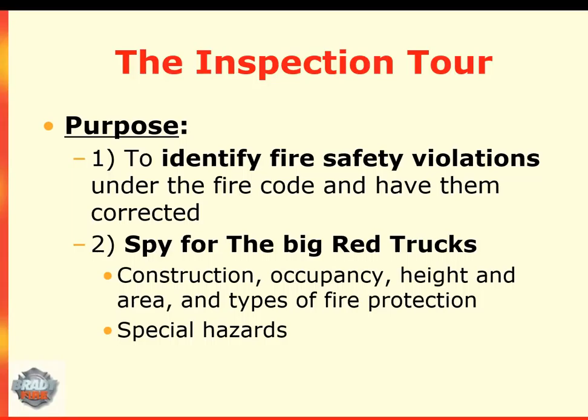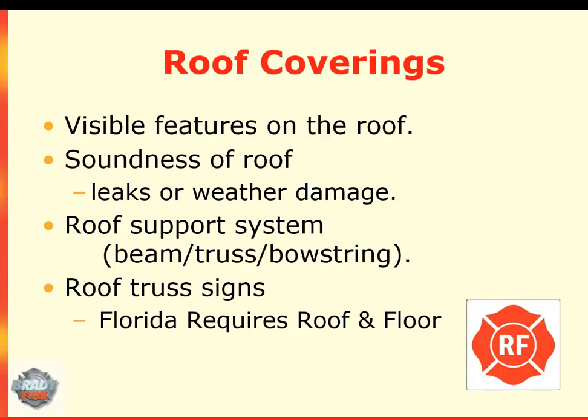However, equally important is your responsibility to gather building intelligence for use by the fire department during emergencies. This includes the type of building construction, the occupancy and use, the height and area, types of fire protection systems, and you need to identify special hazards or firefighter safety concerns. Special hazards may include flammable liquids or hazardous materials. Make sure this information is systematically forwarded to the appropriate first and second response units as well as the communication center. After inspection of the exterior, enter the building and proceed to the roof.